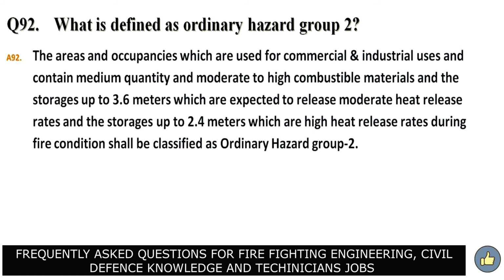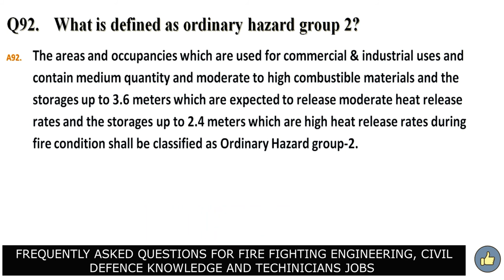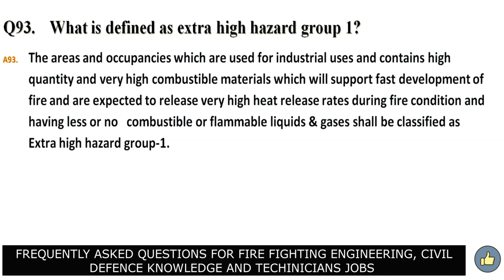The areas and occupancies which are used for commercial and industrial uses and contain medium quantity and moderate to high combustible materials, and the storages up to 3.6 meters which are expected to release moderate heat release rates, and the storages up to 2.4 meters which are high heat release rates during fire conditions, shall be classified as ordinary hazard group 2. What is defined as extra high hazard group 1?